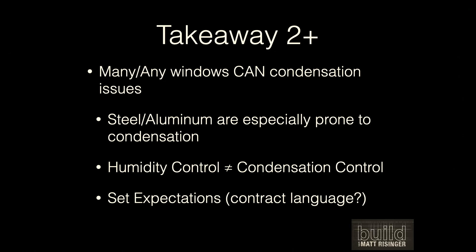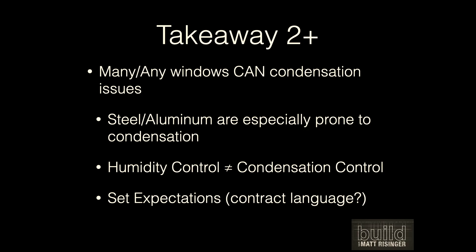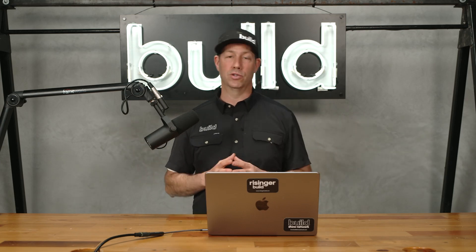So what's the takeaway? From a building science perspective, really any window can have condensation issues — but you'll certainly see it more with non-thermally broken windows like steel or aluminum. A big takeaway is that humidity control does not equal condensation control. That young builder advice to just turn on the bath fan or use your dehumidifier is not necessarily going to control condensation well.